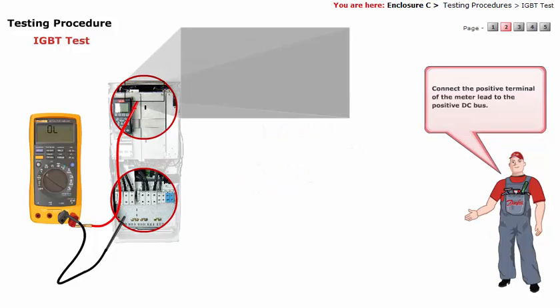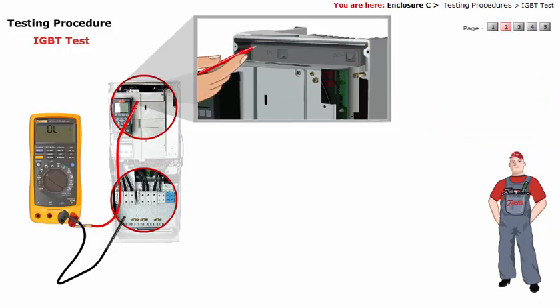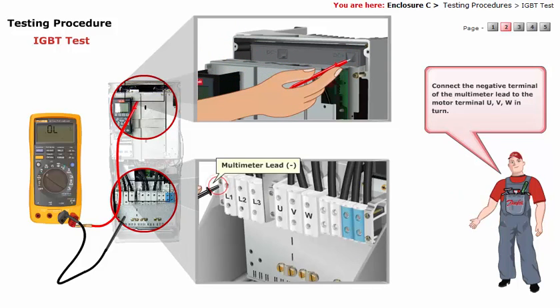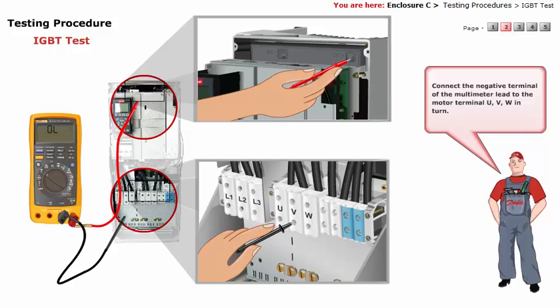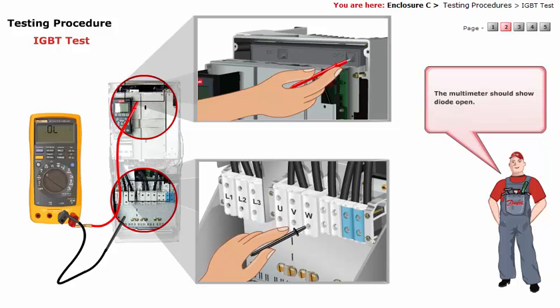Connect the positive terminal of the meter lead to the positive DC bus. Connect the negative terminal of the multimeter lead to the motor terminals U, V, W in turn. The multimeter should show the diode open.